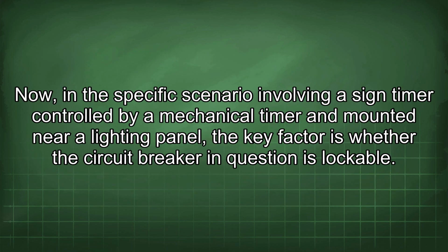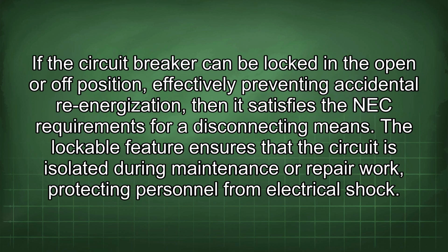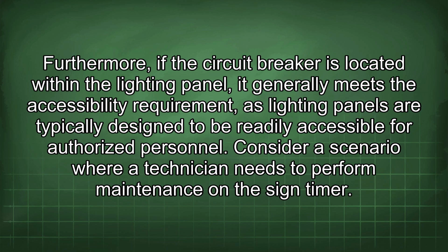Now, in the specific scenario involving a sign timer controlled by a mechanical timer and mounted near a lighting panel, the key factor is whether the circuit breaker in question is lockable. If the circuit breaker can be locked in the open or off position, effectively preventing accidental re-energization, then it satisfies the NEC requirements for a disconnecting means. The lockable feature ensures that the circuit is isolated during maintenance or repair work, protecting personnel from electrical shock. Furthermore, if the circuit breaker is located within the lighting panel, it generally meets the accessibility requirement, as lighting panels are typically designed to be readily accessible for authorized personnel.